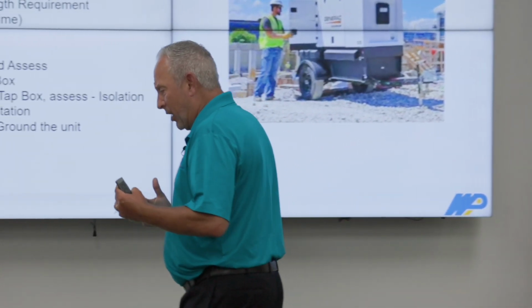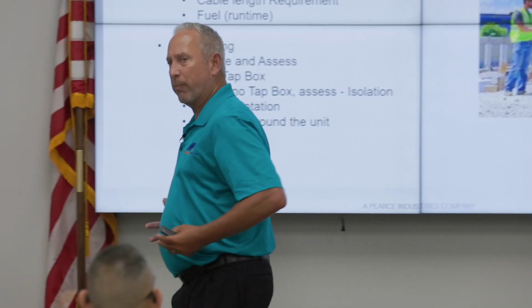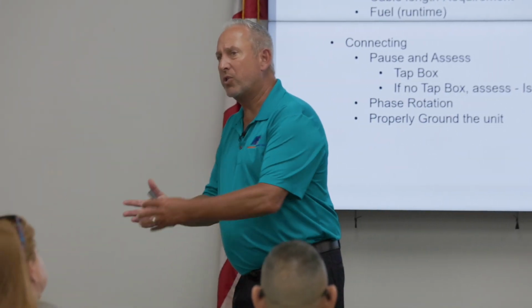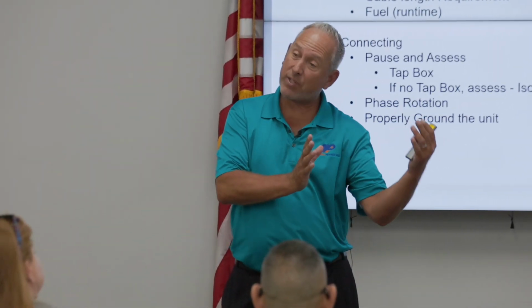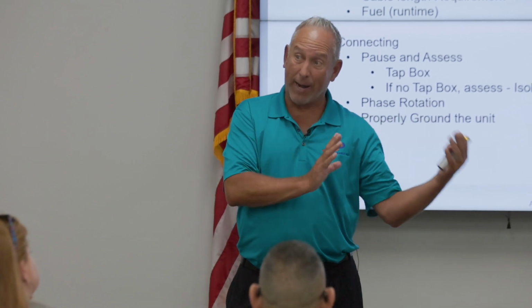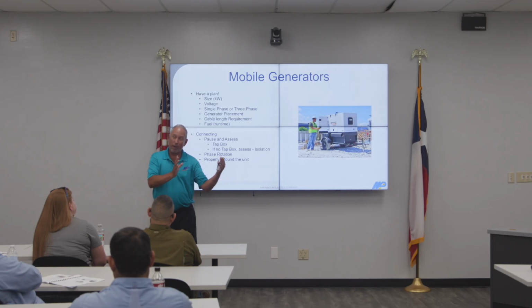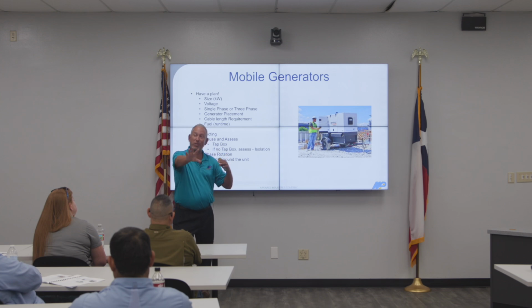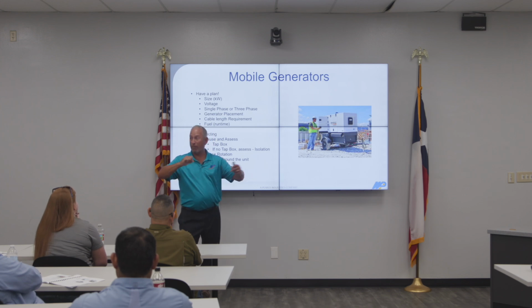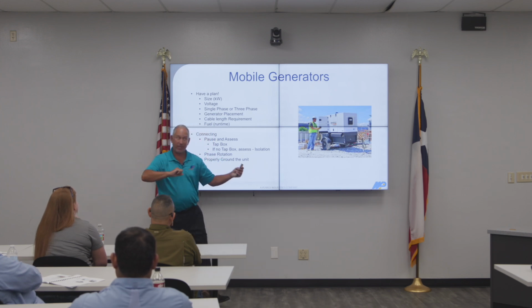Remember, there's two different versions. There's one for a mobile generator because you're bringing power into the building. There's also devices people put on there to test their generators with load bank connections. But with a load bank, you need access to the generator, and that's different than putting power into the building - it's a different throw-over mechanism to be able to load test.